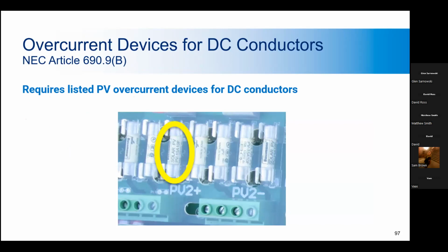So you want to make sure that all the wiring is supported and inaccessible to animals. Again, we talked about having the correct equipment for the application. All conductors and fuses should be DC rated and should be rated for PV. Like I said, for residential you want 600 volts DC rating, and commercial would be 1,000 volts.